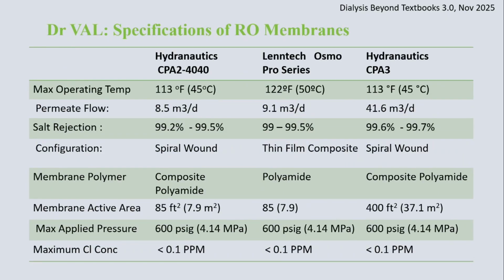So these are some of the membranes which are freely available. What you have is that first one which says 40-40 Hydranautics. It is 4 inches in diameter and 40 inches in length. So for some reason, engineering terminology still uses the British foot-pound system instead of the metric system. You can see that the other ones after that, most of them operate ROs. The optimal performance is somewhere between 37 and 50 degrees. When you go beyond that, you can get damage, though there are now heat-stable membranes available.